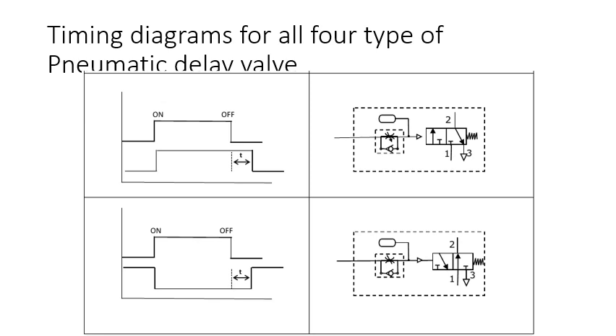On-delay and off-delay describe how you require the response — whether immediately or after a delay. The time delay valve responds slowly compared to a regular direction control valve which responds immediately. The time delay can be set by adjusting the needle valve (flow control) near the chamber — you can set the delay to 5 minutes or 5 seconds by controlling the flow rate of fluid fed to the time delay valve.